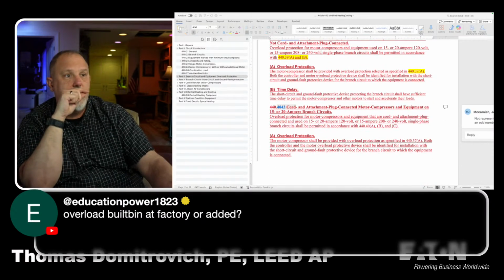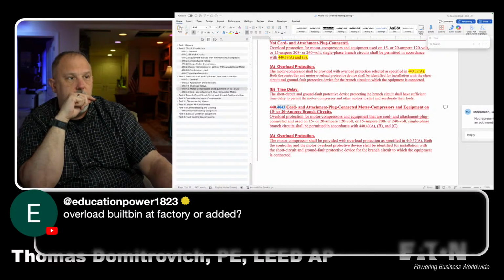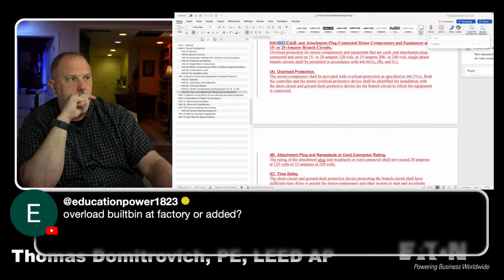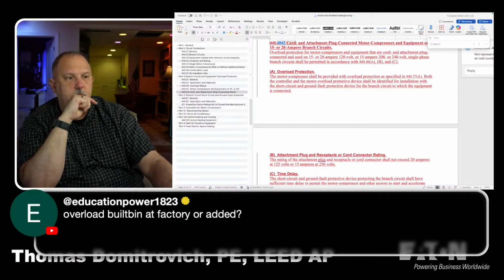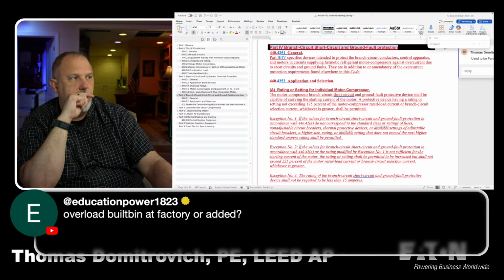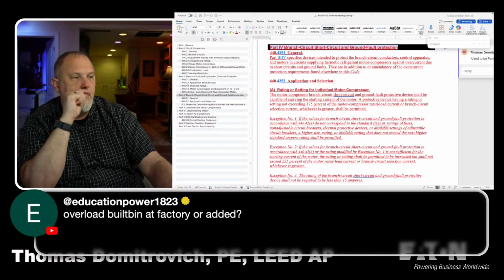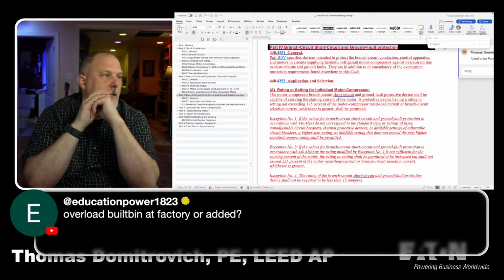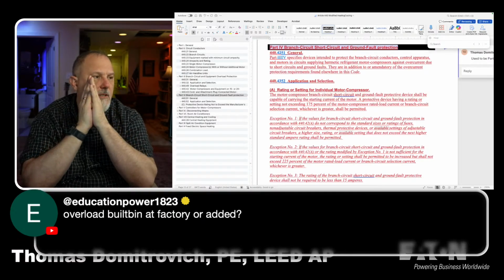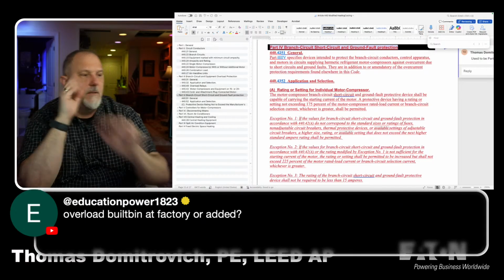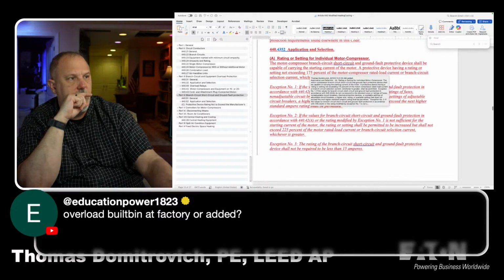Overload protection. All right, so we've got general application and selection, overload relays, motor compressors, and equipment on a 15 or 20 amp branch circuit. And then you have cord and attachment plug connected motor. And then we go to branch circuit short circuit protection and ground fault. The motor compressor branch circuit short circuit and ground fault protective device shall be capable of carrying the starting current of the motor. A protective device having a rating or setting not exceeding 175% of the motor compressor rated. All right, so I got that. All those requirements are there. I don't have a problem with that.